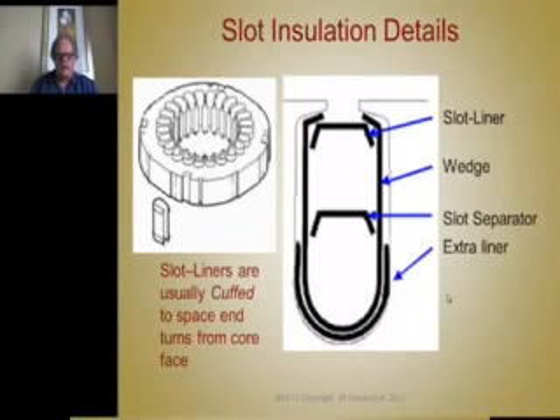Here are some blown up details of the slot insulation. Here you sometimes have an extra liner in the bottom of the slot. This is the main slot liner, and it can be formed like this and inserted by hand. There are hand forming machines and there are automatic forming machines. This is an example of the cuff liner. That's all done by machine. A strip of this stuff goes in a machine and it automatically cuts these and forms these and folds these cuffs. Those are little cuffs. You squeeze this together and put it in a slot, and it pops out, and the cuffs center it and space it up on top of the core like that.